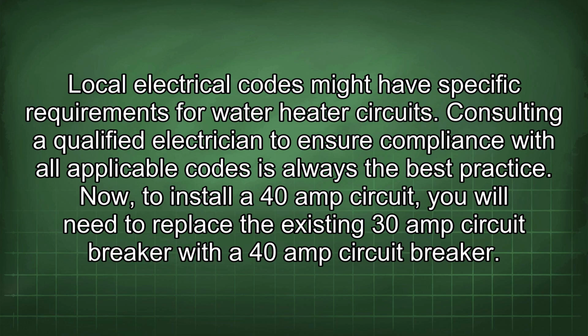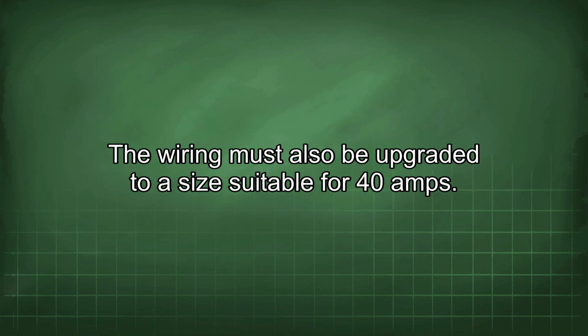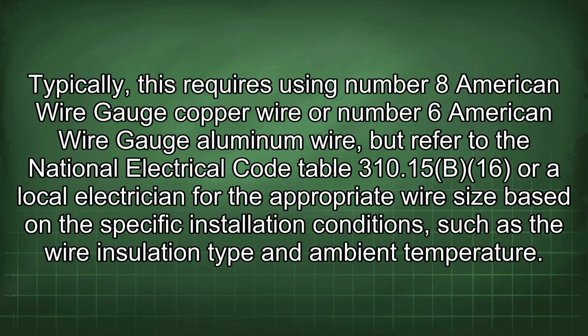Now, to install the 40 amp circuit, you will need to replace the existing 30 amp circuit breaker with a 40 amp circuit breaker. The wiring must also be upgraded to a size suitable for 40 amps. Typically, this requires using number 8 American wire gauge copper wire or number 6 American wire gauge aluminum wire, but refer to the National Electrical Code Table 310.15(B)(16) or a local electrician for the appropriate wire size based on the specific installation conditions, such as the wire insulation type and ambient temperature.